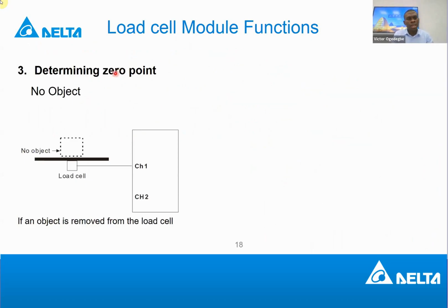Another function again is determining 0 point. So it's possible you want to determine 0 point. Well, how does that work? If you put no object, or if you remove an object from the load cell, from the weight, and there's no load, you can get an indication. This is also control register 200 or D6, like we saw there.